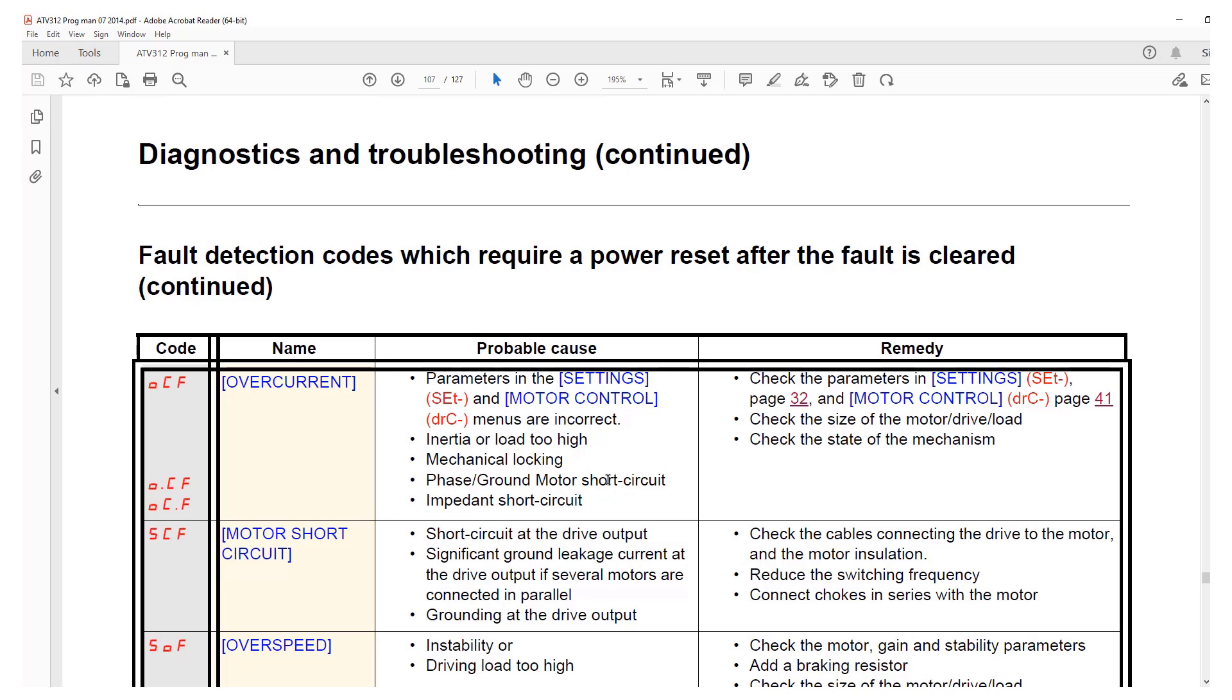It could be a short circuit on the motor or the cables, could be ground short. OC.F is also a short on the motor or the cable, so depending upon which particular OCF it is you need to react accordingly.